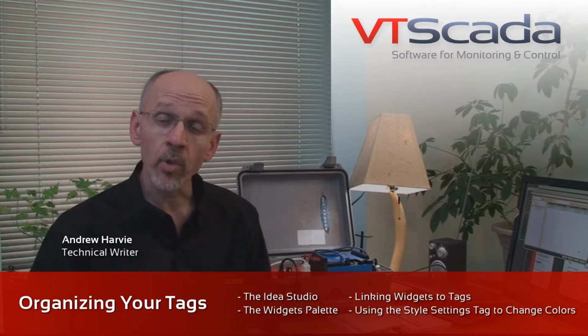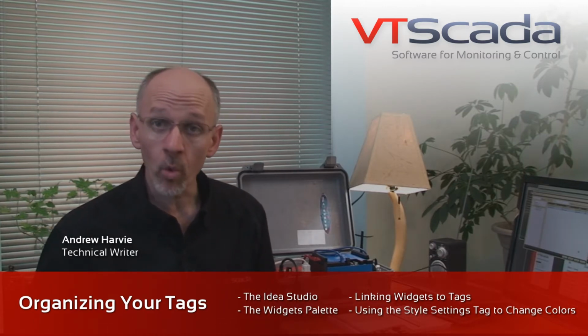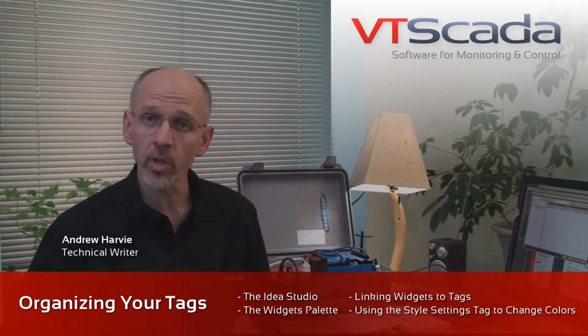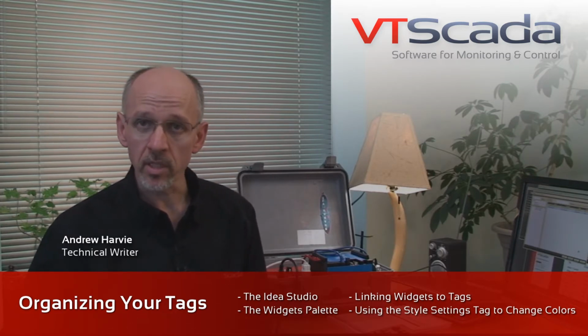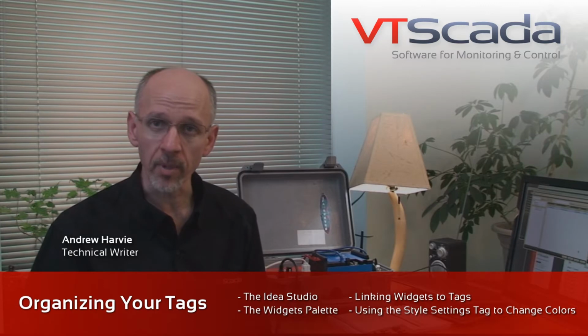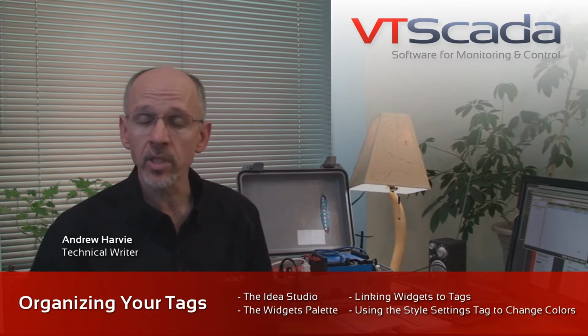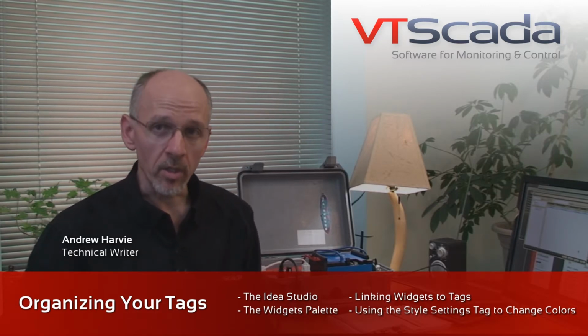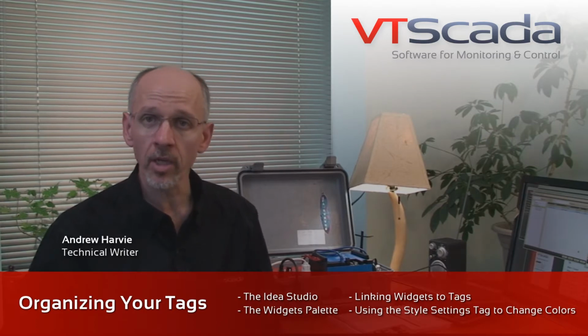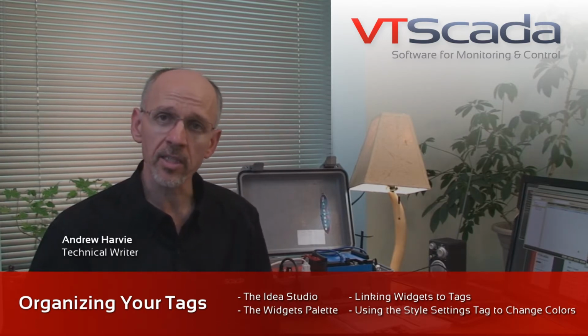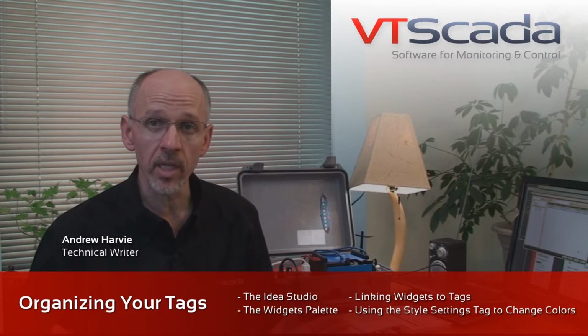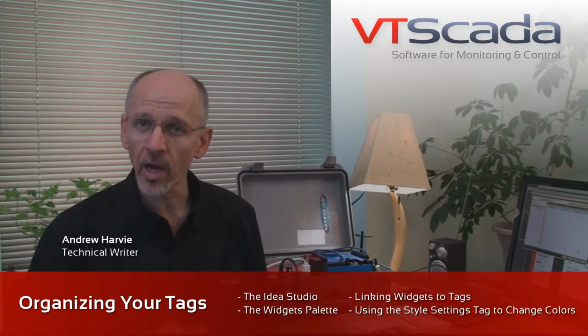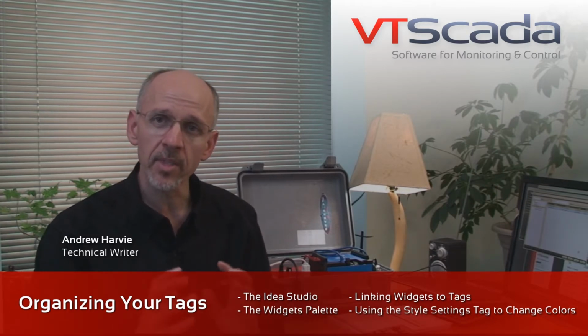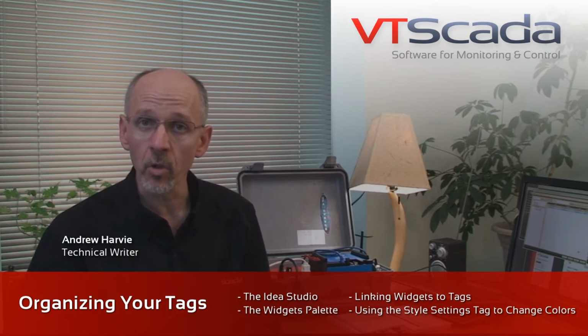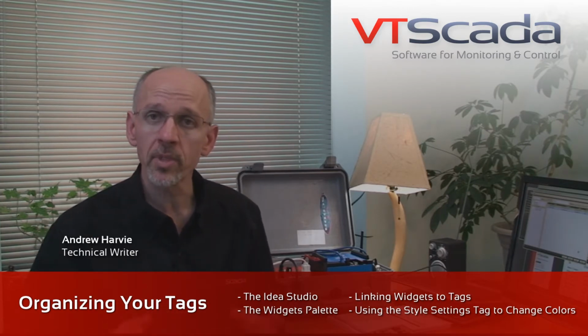Now, we're about to have a problem in that there are 4 motors attached to this demonstration unit. I'm going to need some way to keep my tags organized so I don't lose track of which one is which. In the old days, we used to use the area property of the tags to do that, and we still do. However, we also now have this concept called a context tag. A context tag is anything you want it to be, but it provides context to other tags, encapsulating them together so that all of the I/O for each motor is grouped together.